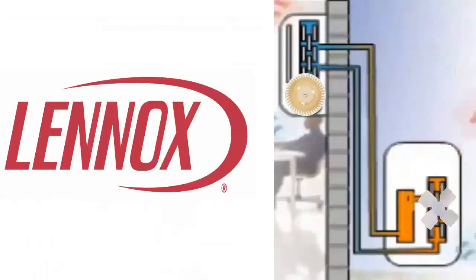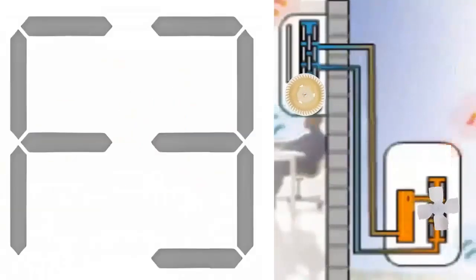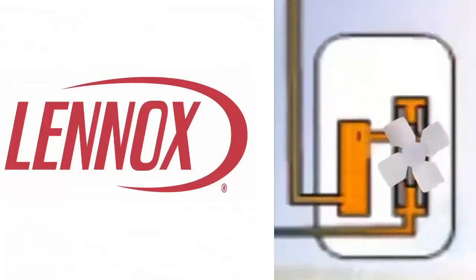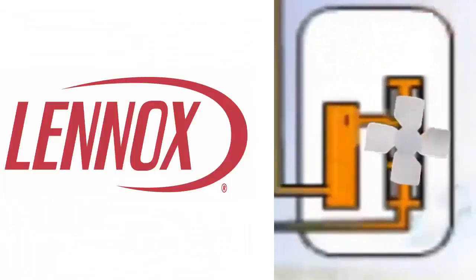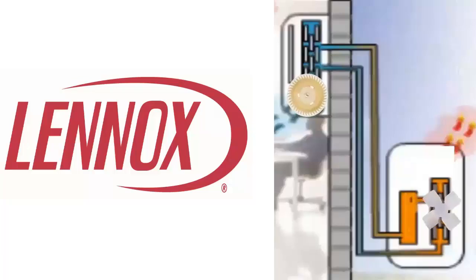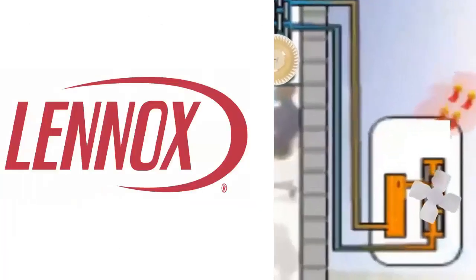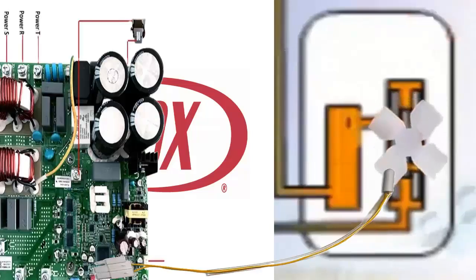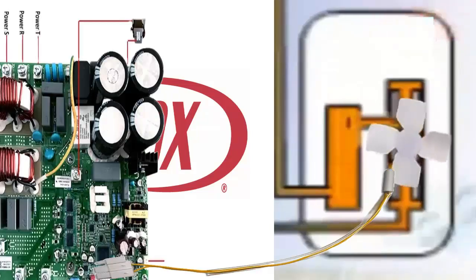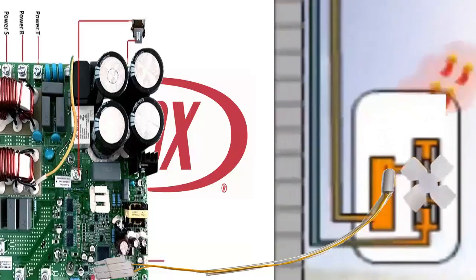Code F3 indicates a problem with the outdoor ambient temperature sensor located in the outdoor unit. This sensor measures the temperature of the air being drawn in by the outdoor fan to average the temperature of the outdoor environment. Code F4 indicates a problem with the outdoor unit coil temperature sensor, which measures the temperature of the refrigerant inside the coil to calculate the refrigerant saturation pressure.